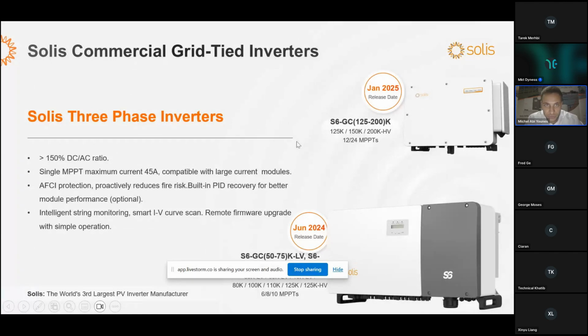Our big on-grid inverter, 400 volts, the 150 to 200 kilowatt, we will be introducing in January 2025. It has a 150% DC to AC ratio. Our MPPT current is up to 45 amp, so around 22.5 amp per string. It has AFCI protection, built-in PID recovery, and for these capacities we also have the function of intelligent string monitoring and IV curve, which reduces the maintenance effort.